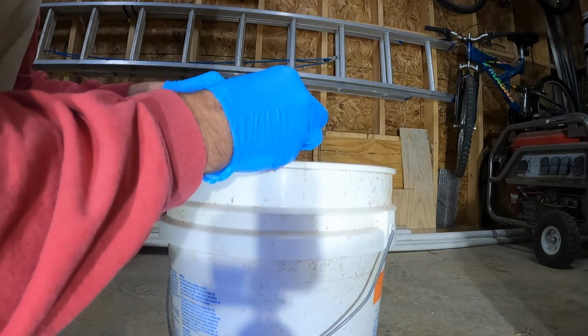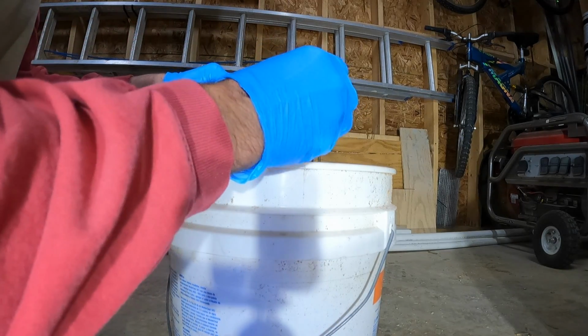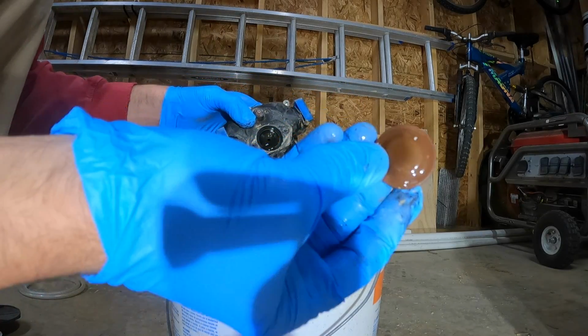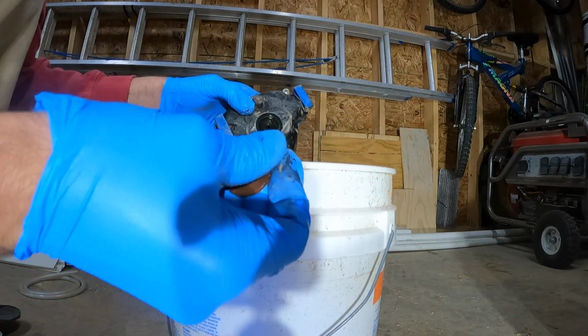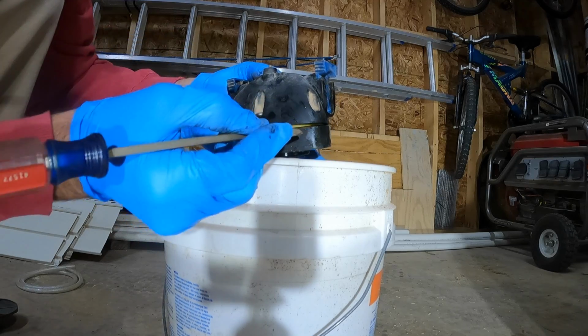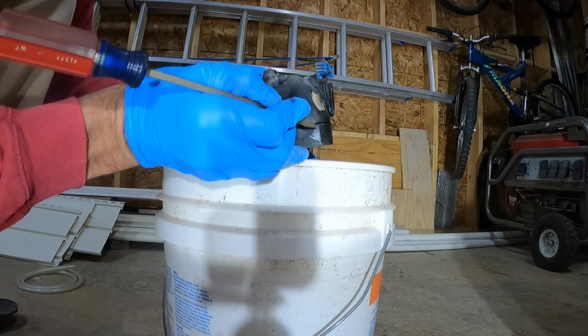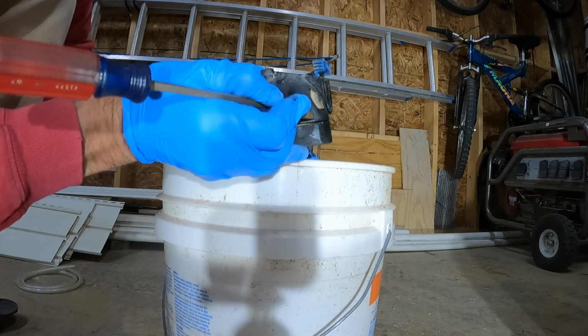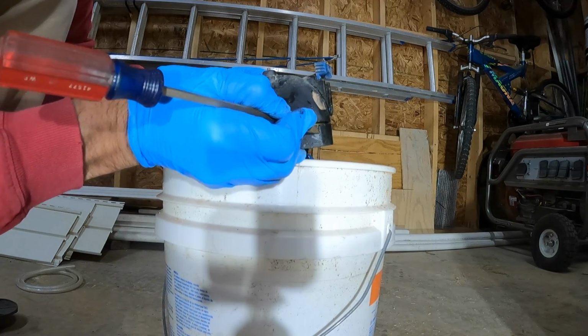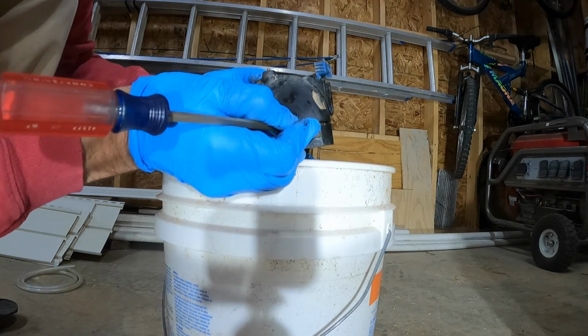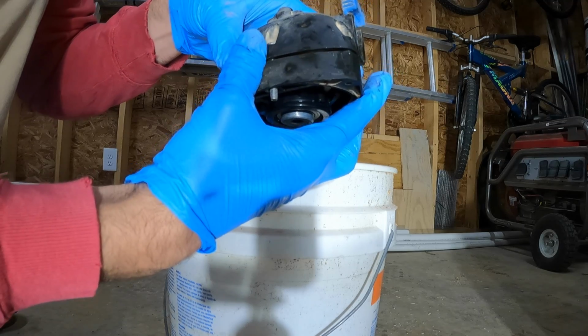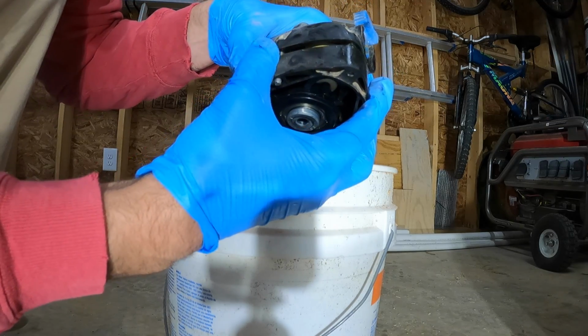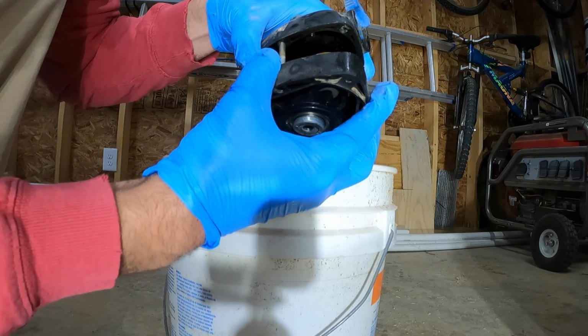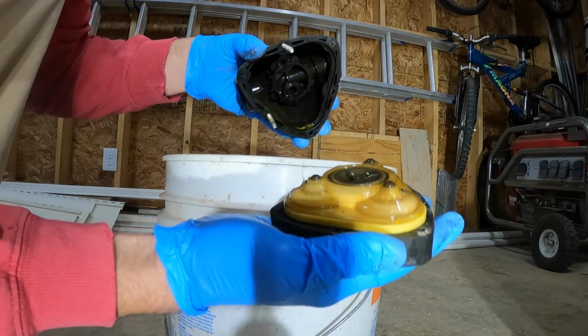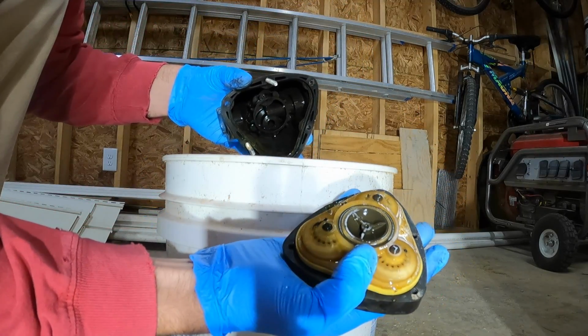You got a small diaphragm under here. You just want to check it and inspect it, make sure it looks clean. One thing you can do before you completely separate the pump is make yourself a little mark with something that will scratch it, so you can see where it goes back together. I'm not 100% sure it really matters which way this orients back on, because all those diaphragms are pretty well the same.